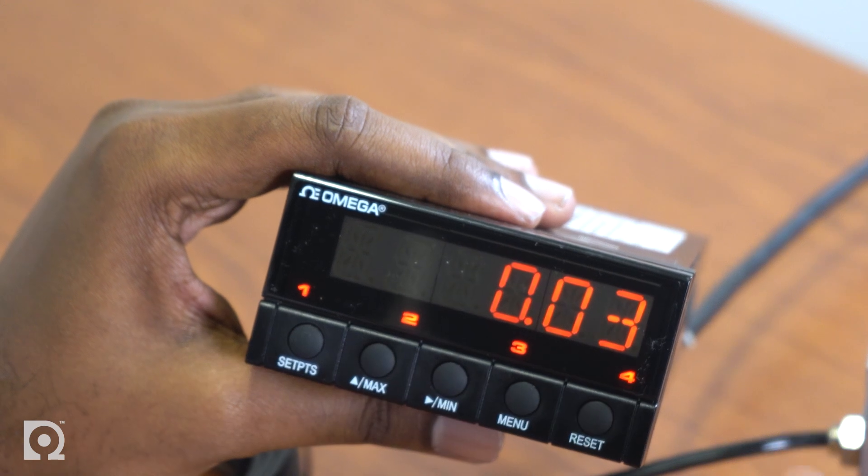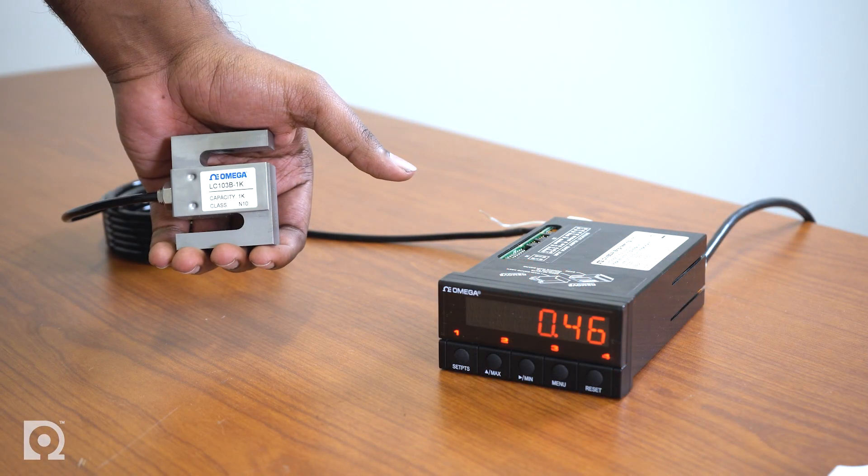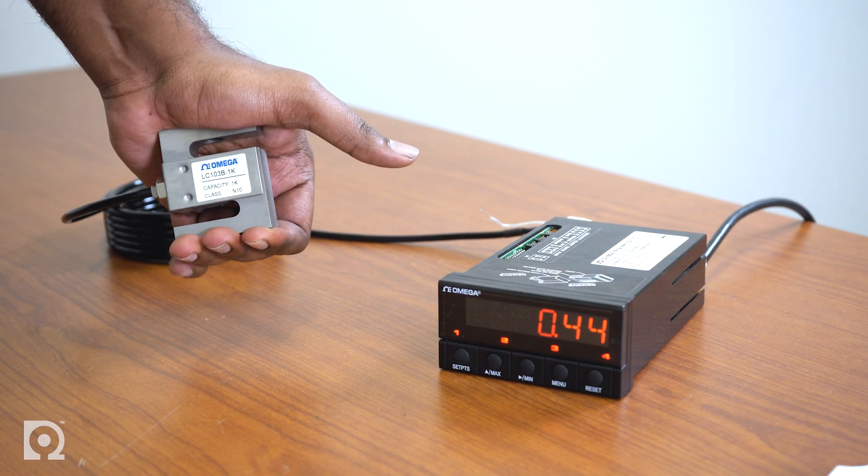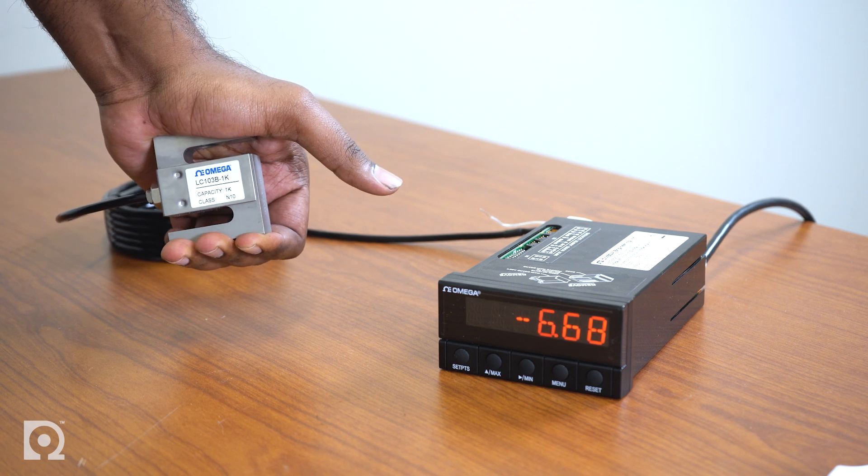And there you have it. We programmed this meter and it reads in pounds force. Now if I manually apply a load on the load cell, you'll see the value of the load cell increasing in pounds force. There you have it. We powered up the meter, connected the load cell to the meter, and configured it to read in pounds force.